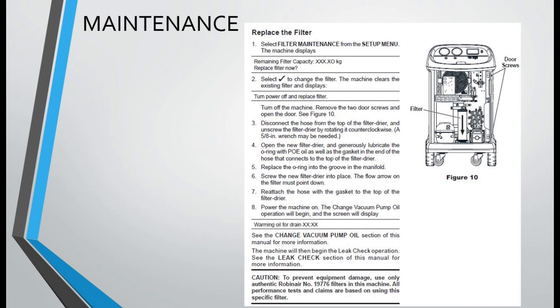See Figure 10. 3. Disconnect the hose from the top of the filter dryer and unscrew the filter dryer by rotating it counterclockwise. A 5/8-inch wrench may be needed. 4. Open the new filter dryer and generously lubricate the O-ring with POE oil as well as the gasket in the end of the hose that connects to the top of the filter dryer. 5. Replace the O-ring into the groove in the manifold. 6. Screw the new filter dryer into place. The flow arrow on the filter must point down. 7. Reattach the hose with the gasket to the top of the filter dryer.